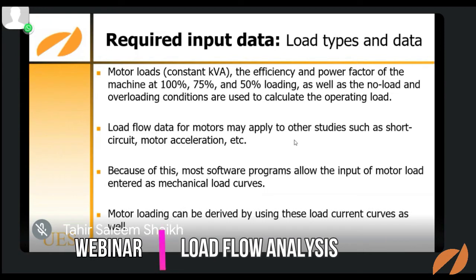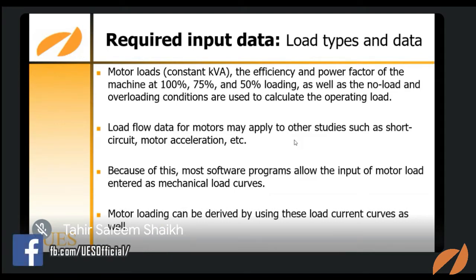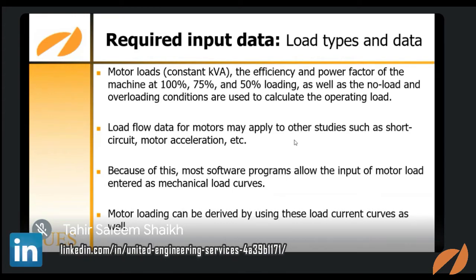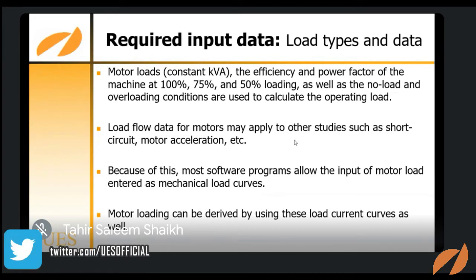Okay, now for the motor loads, these are constant kVA loads. You also have to be careful about how much efficiency you are demanding, either 100%, 75%, or 50%, as well as the loading, that is, how much loading you are putting on that motor. This load flow data for motors may also apply to other studies. So this data is also applicable for short circuit and motor acceleration calculation, especially in ETAP.